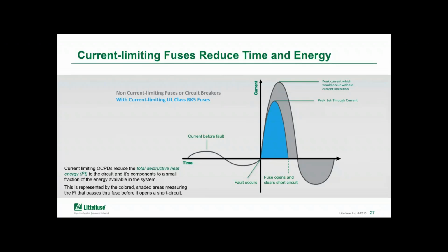Now, UL listed circuit breakers are labeled current limiting, and those circuit breakers must pass a series of short circuit tests and clear the test circuit in less than half of an electrical cycle. Now, UL doesn't impose different I²T limitations for those different breaker ratings. That's something you would have to work out with the breaker manufacturer. And the I²T that I'm mentioning there is really the amount of energy that's passing through the protective device. So fuses must also clear the circuit in a half cycle, just like a breaker, in order to be called current limiting. And being a fuse company, of course, we recommend the use of current limiting fuses in many applications as one of the important things you can do to reduce the arc flash energy.